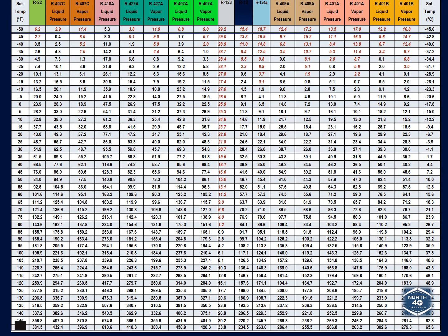So how would you do that? Well, you would not be able to do your normal superheat or subcooling without doing some investigating on figuring out what the temperature pressure relationship is, right? Because on the dial style gauges, with the temperature on the inside and the pressures on the outside, if they're actually 410A gauges, that temperature that's in the middle correlates to the 410A pressure and temperature relationship, right? For every pressure, it correlates to a particular temperature. On different refrigerants, it's going to be different. So we need to figure out what it would be with an R22 setup.